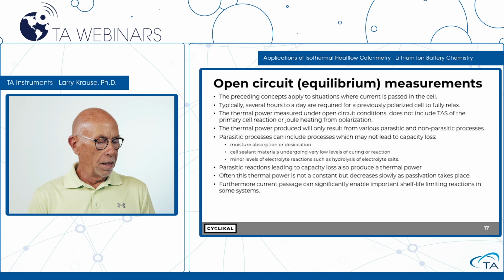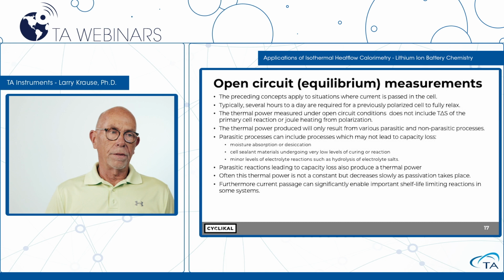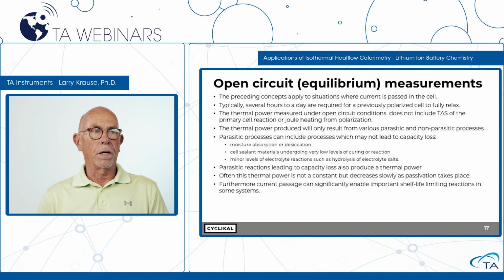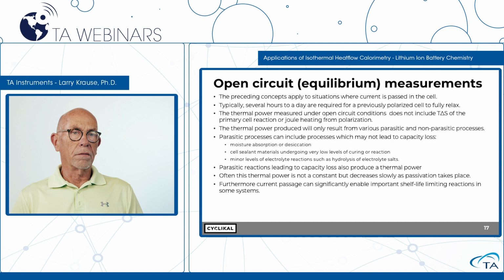Minor levels of electrolyte reactions that don't necessarily degrade the capacity. For example, in a lithium-ion battery, you always put the battery together and it's going to have some moisture in the electrolyte, and that may be 15 to 20 parts per million water. And when the salt is combined with that, there's a low level of hydrolysis that will go on, and that produces heat. And that does not necessarily degrade the capacity of the battery.